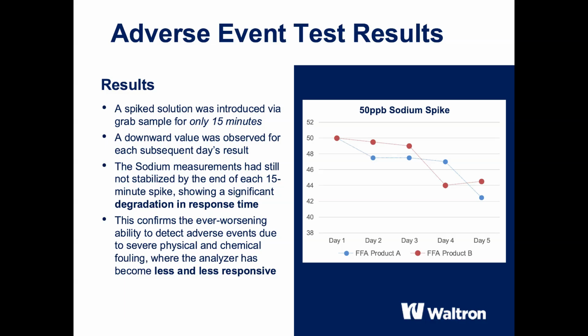The graph clearly shows 2 things. First, the analyzer's response time deteriorated dramatically. On none of the days did the reading reach a stable plateau within 15 minutes. The sensor response has become too slow to detect a rapid increase. Secondly, and even more critically, the device's ability to detect the spike at all decreases day by day.